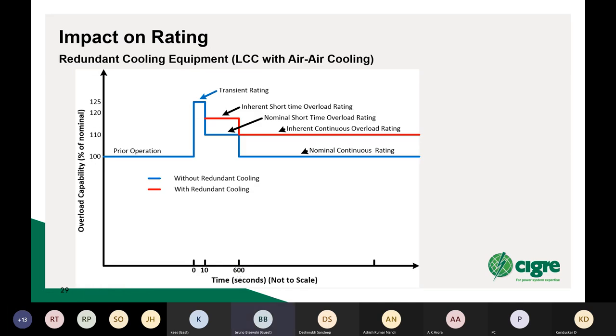This diagram just explains a little bit of the concepts that we had covered in the rating earlier. Assuming that we have prior operation at 100%, and then we have an event which requires overload, we can typically get a transient overload, which again is governed by the thermal time constant of the thyristors or IGBTs and the cooling systems associated with those. That is really in the 1 to 10 second range, and it's not adjustable or affected by the redundancy in the cooling. Whereas the short time overload rating and the inherent continuous ratings would be increased if you have redundant cooling compared to the value that you could achieve without redundant cooling, which we are calling the nominal continuous rating.